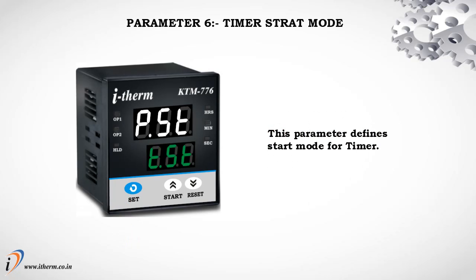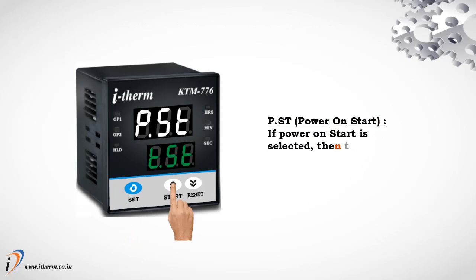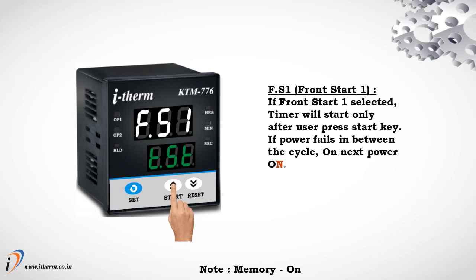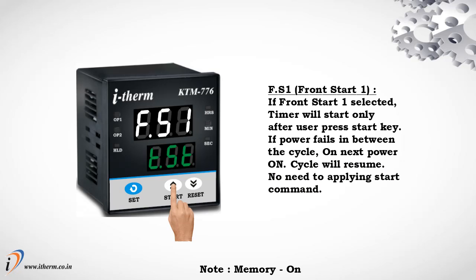Parameter 6: Timer Start Mode. This parameter defines the start mode for the timer. Power On Start: if selected, the timer will count from power on. Front Start 1: if selected, the timer will start only after the user presses the Start key. If power fails during the cycle, on next power on no need to apply the start command again.